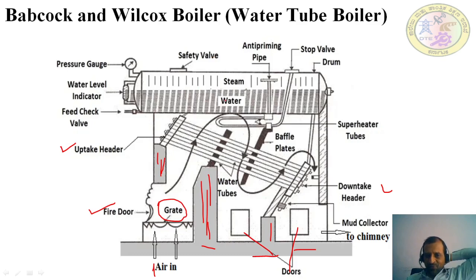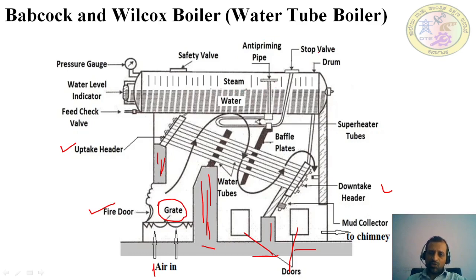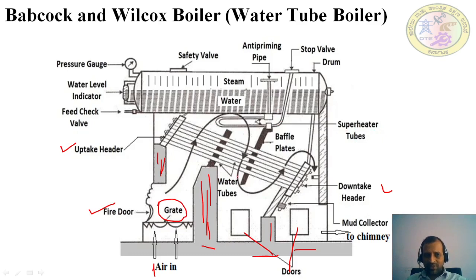If the pressure exceeds the maximum, the safety valve opens to make the boiler safe. The anti-priming pipe is used because steam can contain some water particles; those water particles are separated by the anti-priming pipe. Through the stop valve you can get the steam for further applications. There is also a superheater tube here.